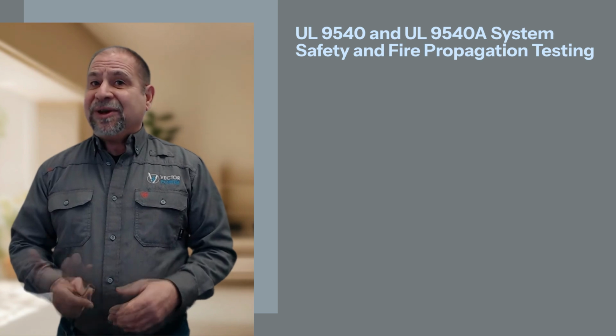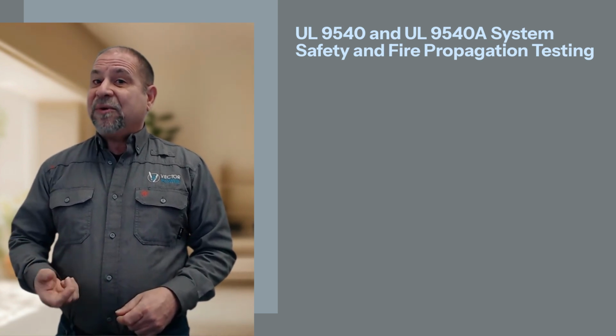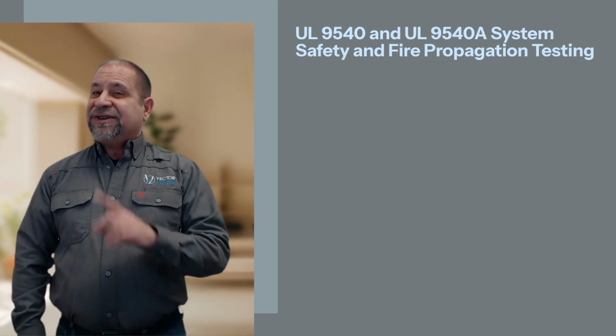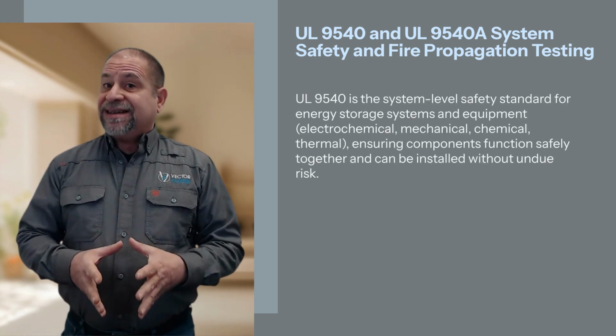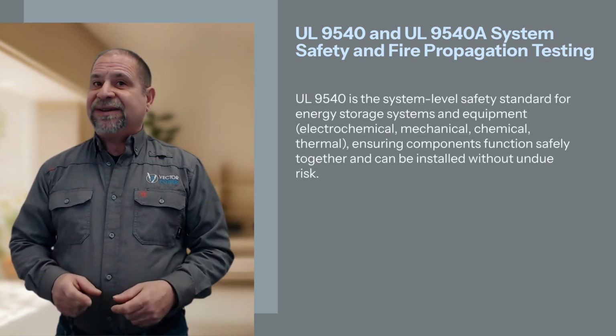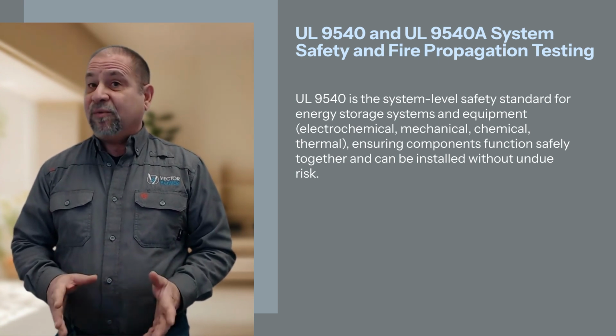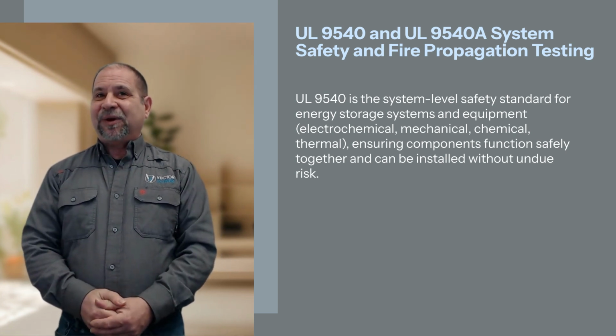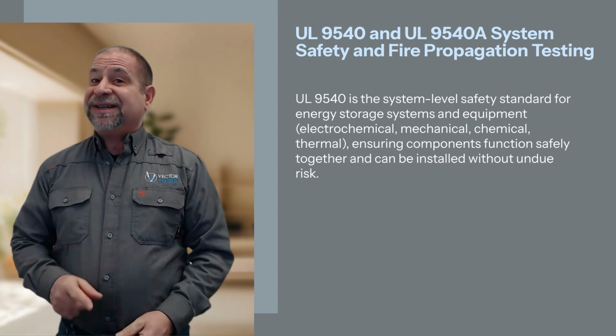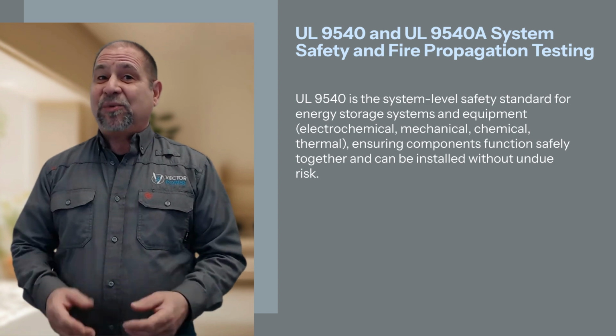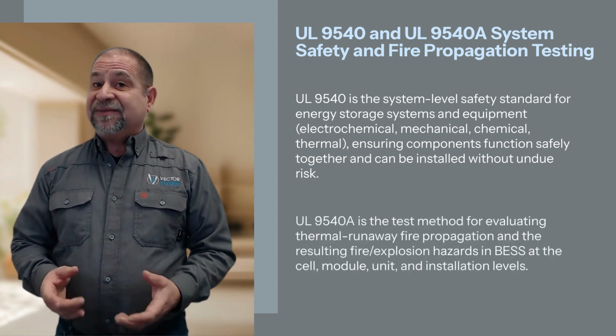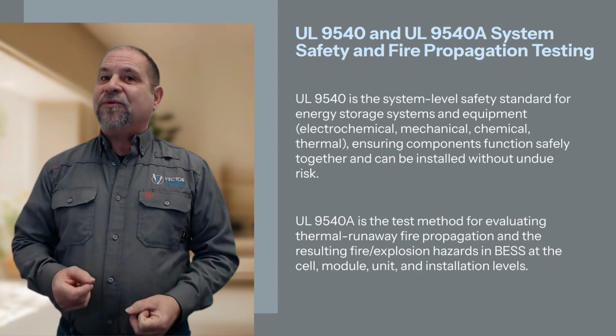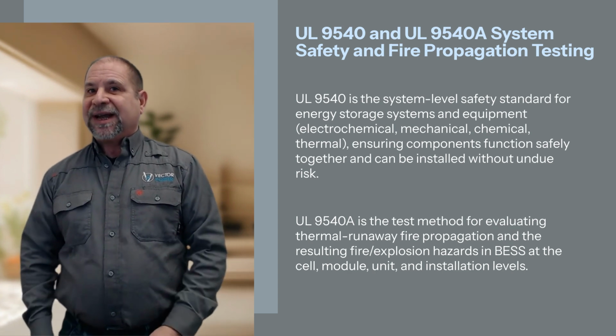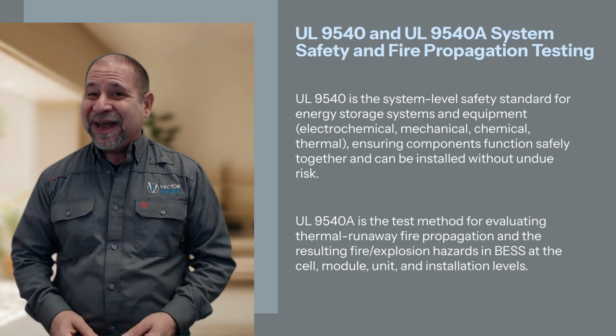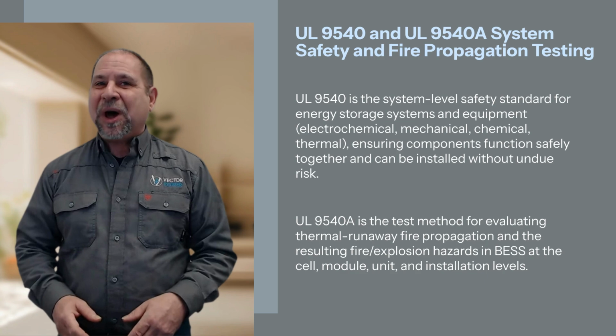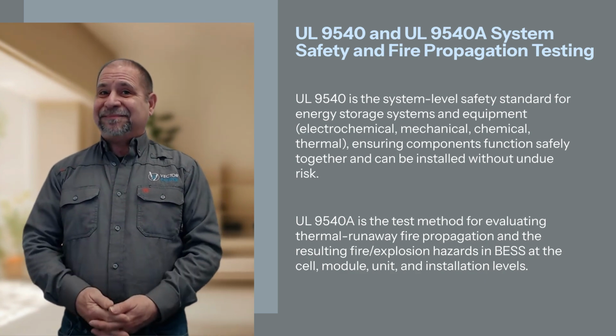UL 9540 and UL 9540A, System Safety and Fire Propagation Testing. UL 9540 is the system level safety standard for energy storage systems and equipment, electrochemical, mechanical, chemical, or thermal, ensuring components function safely together and can be installed without undue risk. UL 9540A is the test method for evaluating thermal runaway fire propagation and the resulting fire and explosion hazards in battery energy storage systems at the cell, module, unit, and installation levels.